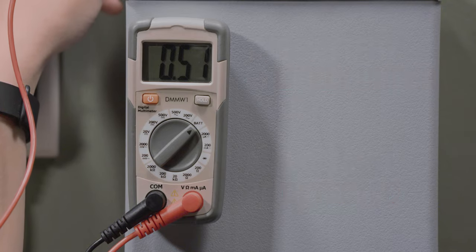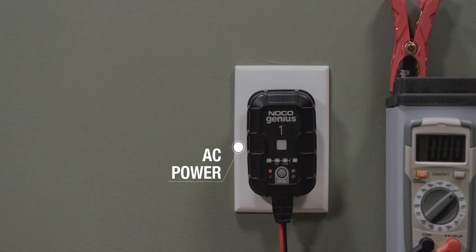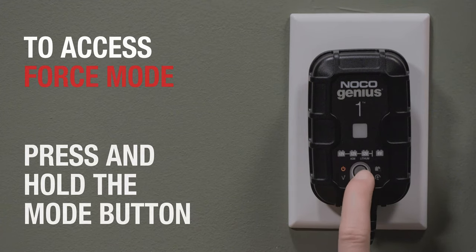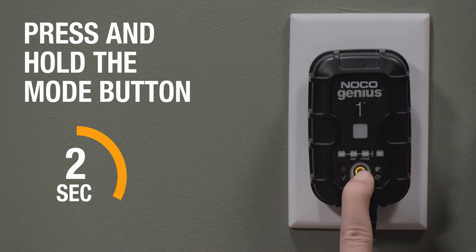To access force mode, ensure the charger is connected to AC power and has a secure connection to the battery. Then press and hold the mode button for approximately 2 seconds.